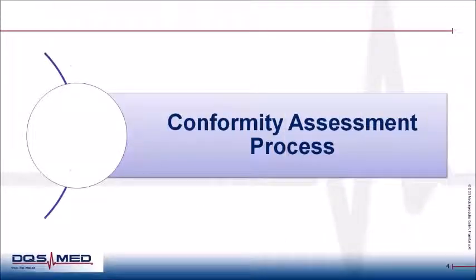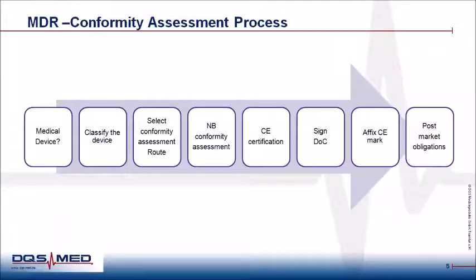So let's start with the conformity assessment process. The MDR conformity assessment process is basically similar to the existing medical device directive. It is the same. So it all starts with first deciding whether the product which you have to market is a medical device or not. If it's a medical device, you need to first classify the device based on the intended use. Once you have classified the device, you need to select the conformity assessment route and then need to check whether a notified body involvement is required or not.